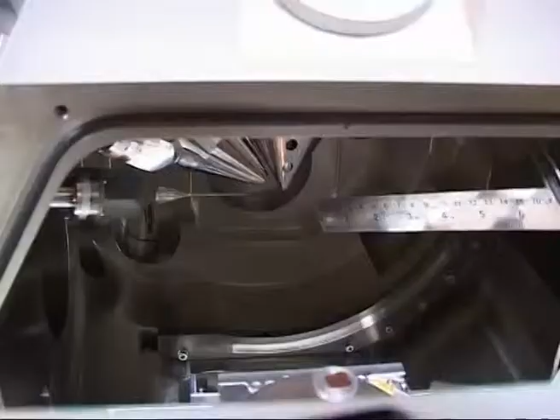As you can see inside the chamber, this is the electron beam, this is the ion beam, and these three are the precursor gas nozzles. One has to be very careful handling these precursor gases, because if you incidentally hit the substrate, the tip might be broken. The substrate is mounted over here, and the precursor gases come very close to this substrate, around 100 micron, so one has to be very careful while mounting the sample. The distance from the top surface to this base is kept within some permissible limits, and it should not go beyond that, otherwise it might hit the electron pole pieces, the ion column and the precursor gases. Then when we close in, the substrate reaches close to the precursor gases.